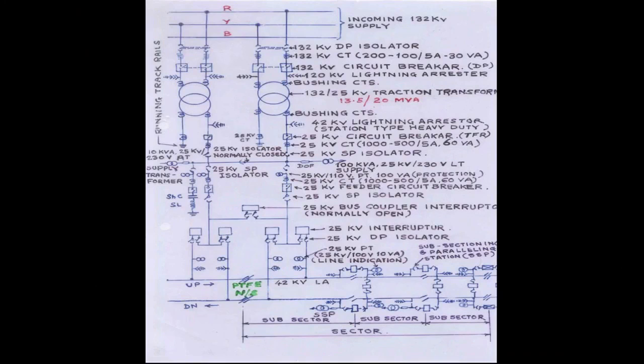What is the impedance moving? How much is the impedance? Because we are comparing the set impedance with the moving impedance, or the measured impedance, V by I. So the relay is finally measuring voltage and current and calculating the impedance.